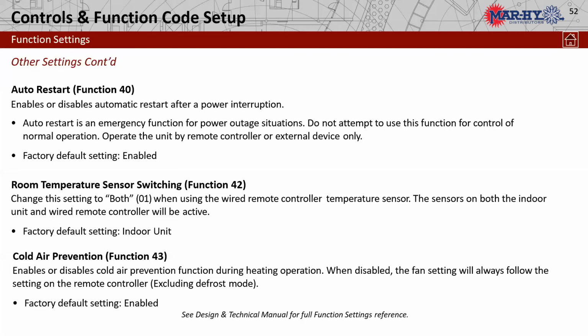So this is where we try to reduce the airflow in the heating mode, in the thermal off mode. At this time, I have not found a thermal off for the fan. If we leave it disabled, it will follow the settings on the thermostat, the fan setting speeds. If we enable, it will take it to low in the thermal off mode, which I know sometimes can be kind of tricky in the heating mode of having a fan that constantly runs. There again, you know, people don't like air blowing on them when it's not got heat in it.